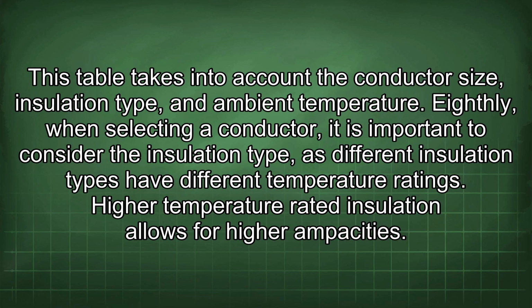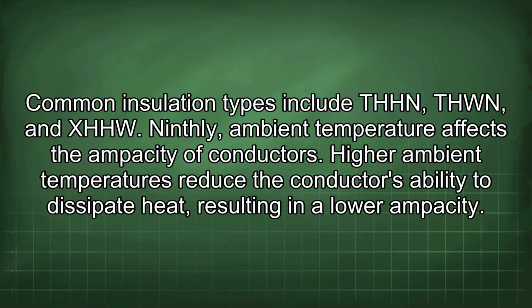Eighthly, when selecting a conductor, it is important to consider the insulation type, as different insulation types have different temperature ratings. Higher temperature rated insulation allows for higher ampacities. Common insulation types include THHN, THWN, and XHHW.